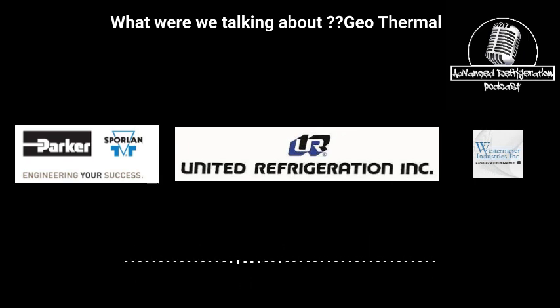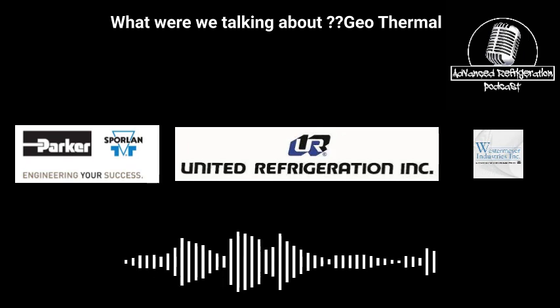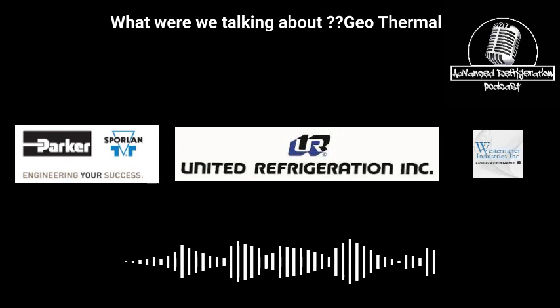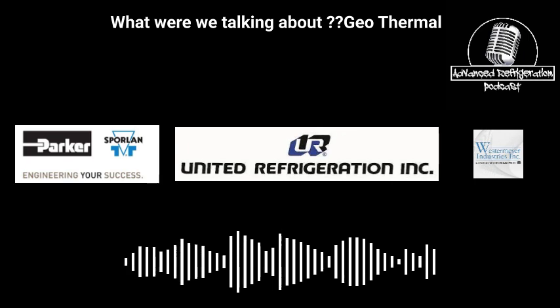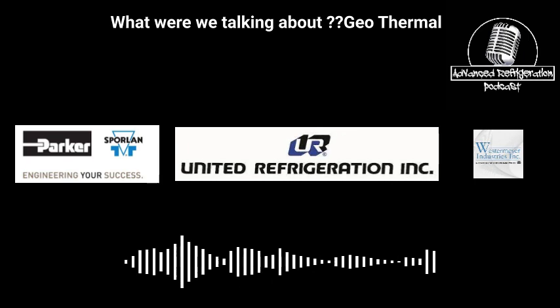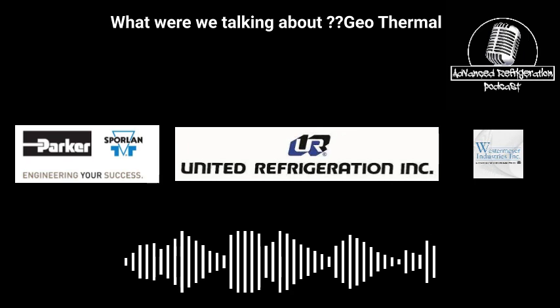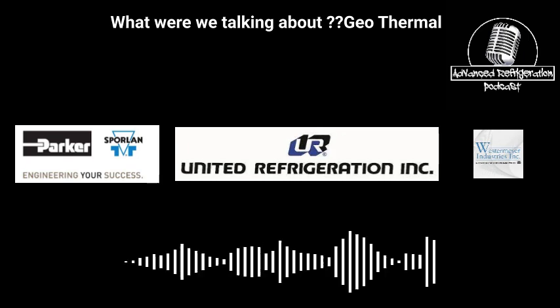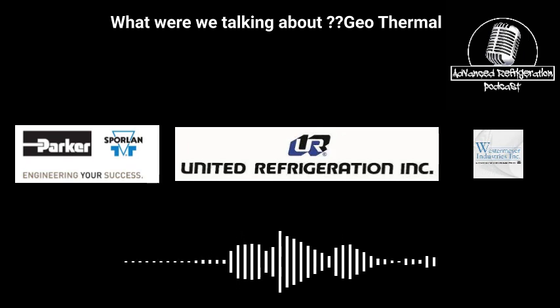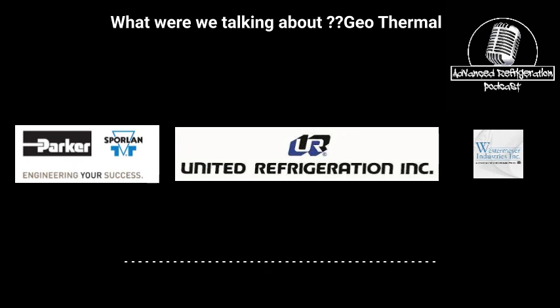Yeah, for sure. And you said these were the condensers that were totally clapped to shit, right? Oh, these ones? Yeah. This thing was begging for a sprinkler at 50 today. Begging. It's running 295 pounds a head. There were 6 sprinklers underneath 3 condensers at this store. There's 5 total. They had a booster pump on the roof, just to get the flow.